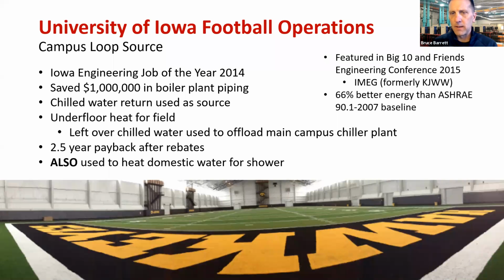Some great jobs we've done here at Multistack, employing the use of heat that's already on the campus. University of Iowa, a very cold climate. They built an indoor football practice facility. They were going to bring boiler plant piping almost a mile to this facility to do the underfloor heat. The engineer explored some different options. They had a chilled water return main on the campus, a big 60-inch pipe that was always full of 50, 55 degree water. We're extracting heat out of that pipe, dumping it back into the return to the campus, kind of a quasi geothermal application, but they saved well over $1 million in boiler plant piping. They're using chillers to both heat the underfloor system as well as do domestic hot water heat for all their showers, for all the football players' showers, their therapy tanks, etc.